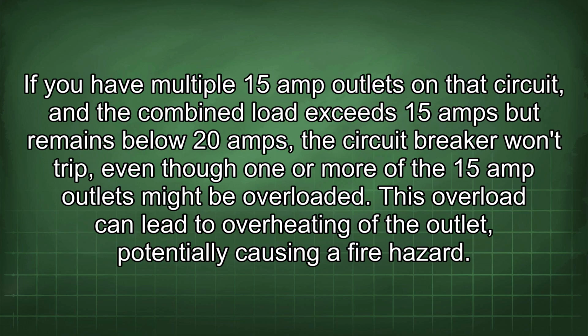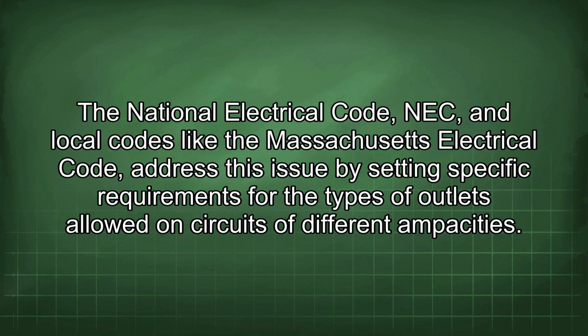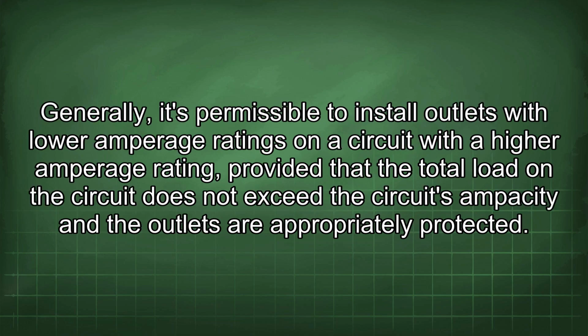If you have multiple 15 amp outlets on that circuit, and the combined load exceeds 15 amps but remains below 20 amps, the circuit breaker won't trip, even though one or more of the 15 amp outlets might be overloaded. This overload can lead to overheating of the outlet, potentially causing a fire hazard. The National Electrical Code, NEC, and local codes like the Massachusetts Electrical Code address this issue by setting specific requirements for the types of outlets allowed on circuits of different ampacities. Generally, it's permissible to install outlets with lower amperage ratings on a circuit with a higher amperage rating, provided that the total load in the circuit does not exceed the circuit's ampacity and the outlets are appropriately protected.